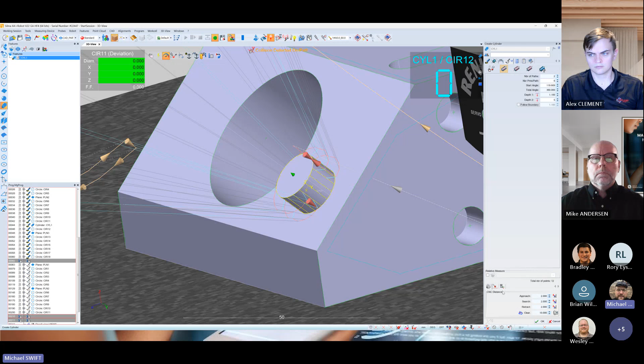I also have the option down here that I like to show, which is where we can control the 5-axis parameters inside the software. Currently it's set to automatic, and automatic to us is the most efficient way to collect the data using the hardware that we have, in this case the PH20. Since we have the PH20 here, it's going to try to do head touches if it can. It's the most efficient, most accurate way to use the hardware. So I'm going to come down here.